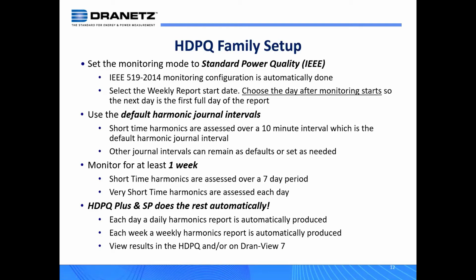It's going to set itself up to do all the statistical analysis and the recording for the harmonics, as well as the reporting for the harmonics, which includes how often the instrument records to memory, which is those journal intervals. So you don't have to do anything. And again, as I mentioned before, monitor for at least 1 week, because the requirements in IEEE 519-2014 is for short time harmonics. Those are assessed over a 7-day or 1 week period.